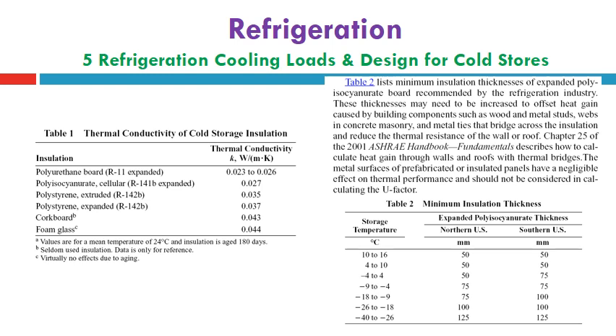northern USA and southern USA based on the storage temperature range starting from 10 to 16, 4 to 10, minus 4 to 4, minus 9 to minus 4, minus 18 to minus 10 to minus 9, minus 26 to minus 18, and finally minus 40 to minus 26. The thickness of expanded insulation materials used can range from 50 millimeters up to 125 millimeters in both northern US and southern US, as can be seen in this Table 2.